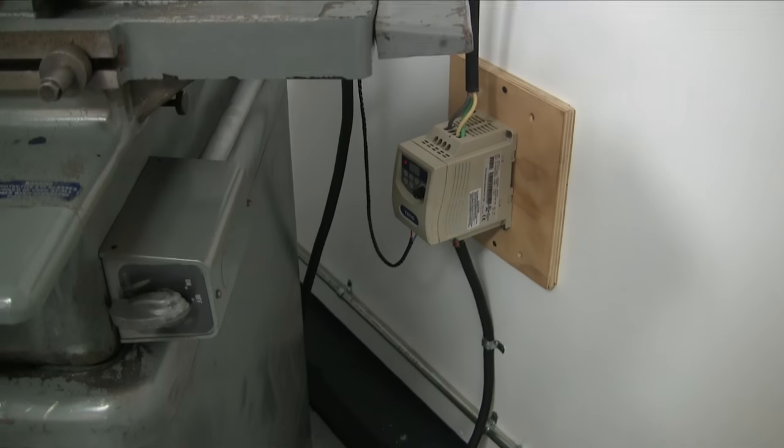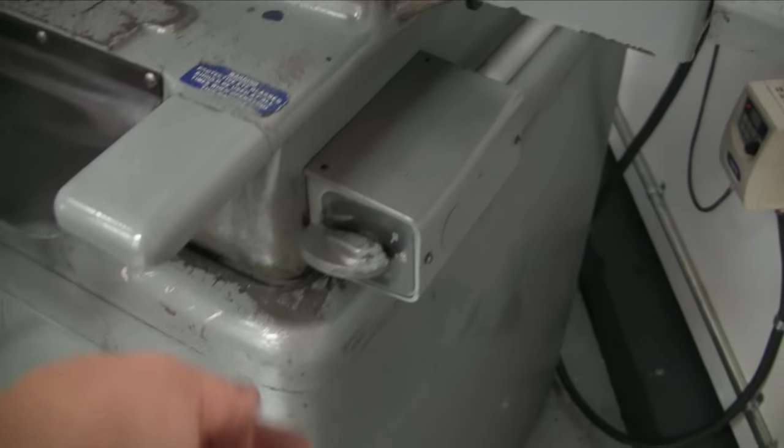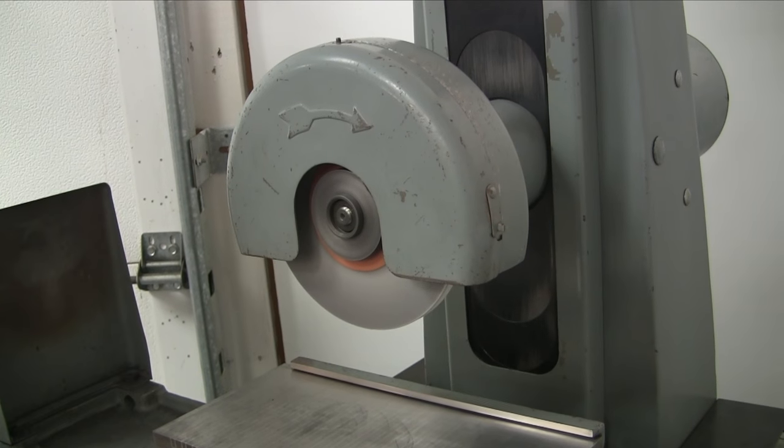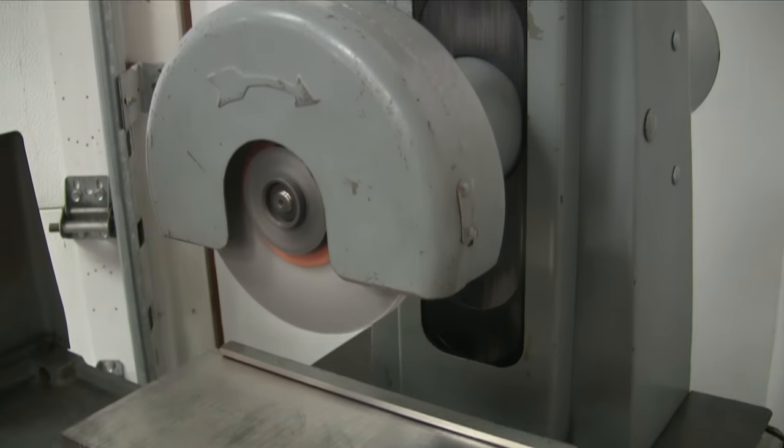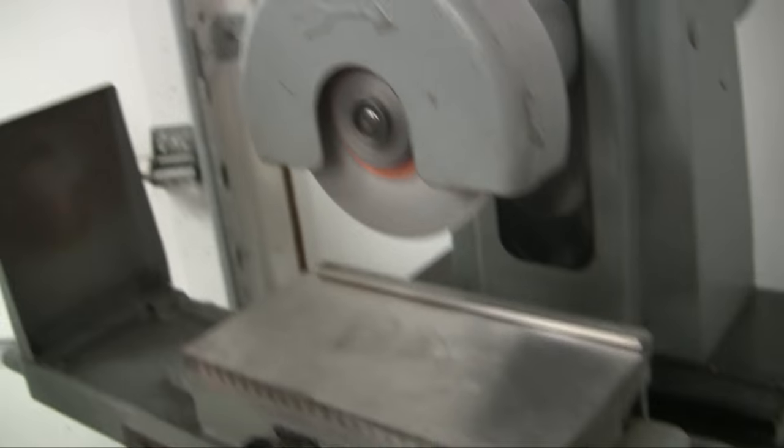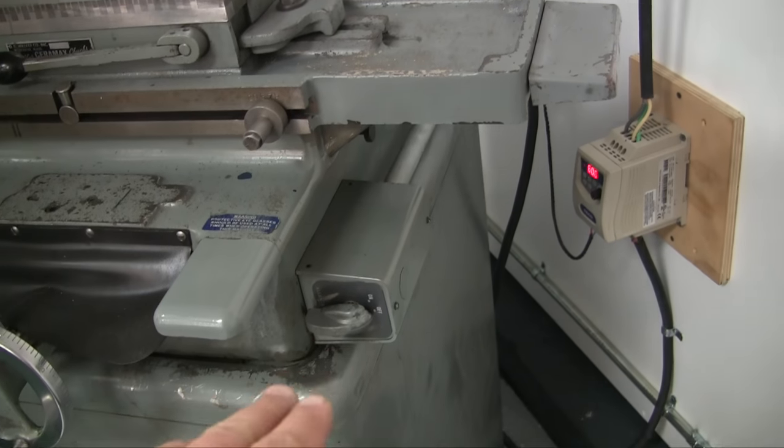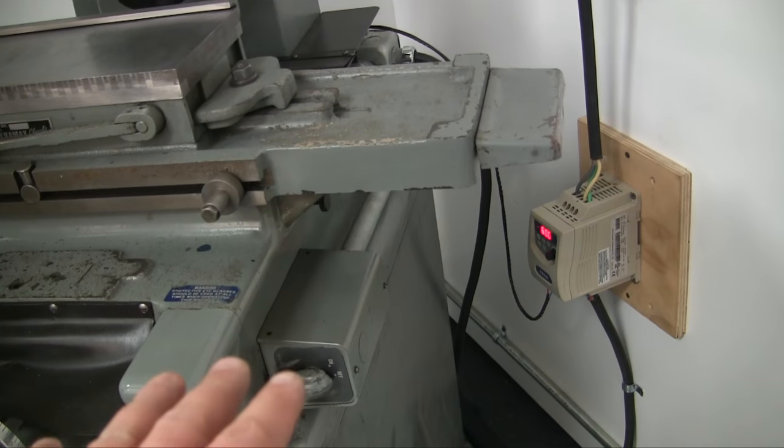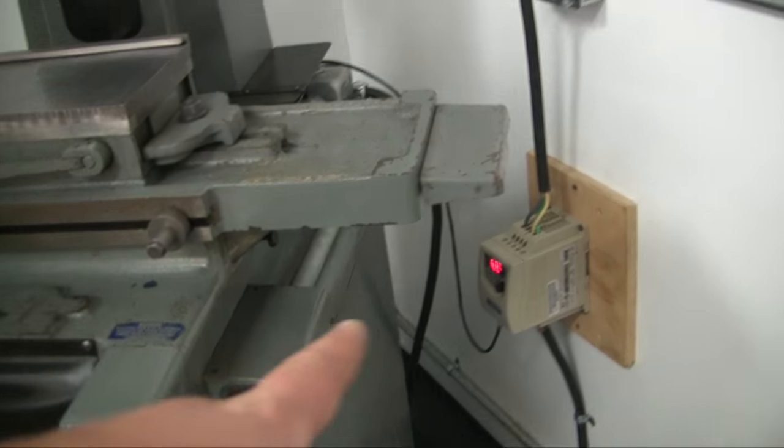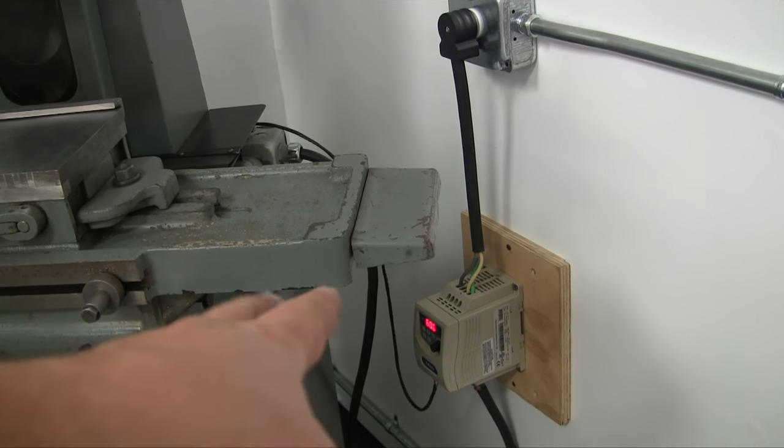But without further ado, it works! So basically, in short, the drum switch really just issues a start or run command and a stop command to the VFD. You've got to put it in the correct terminals—I believe the terminals are three and five.